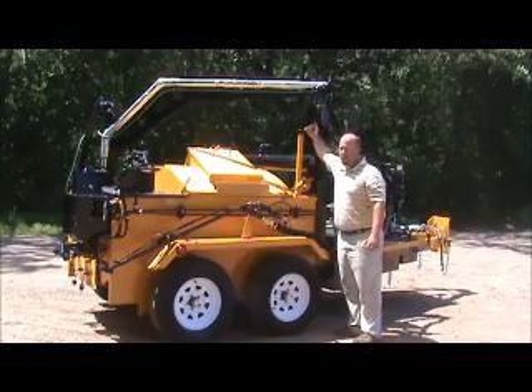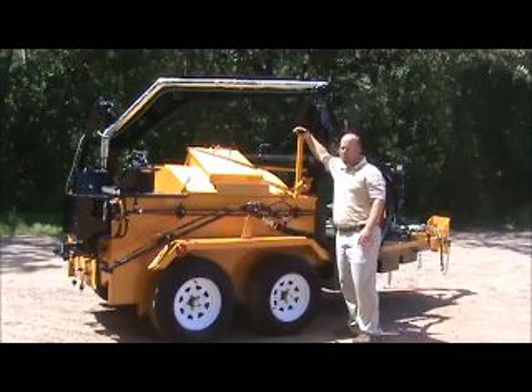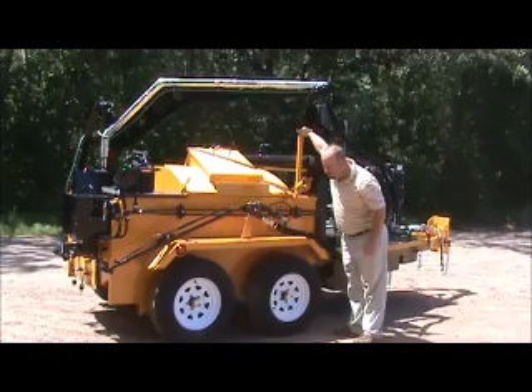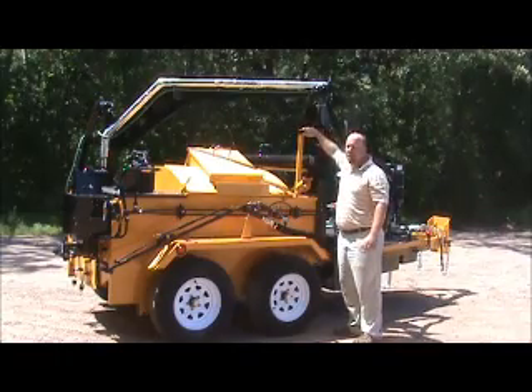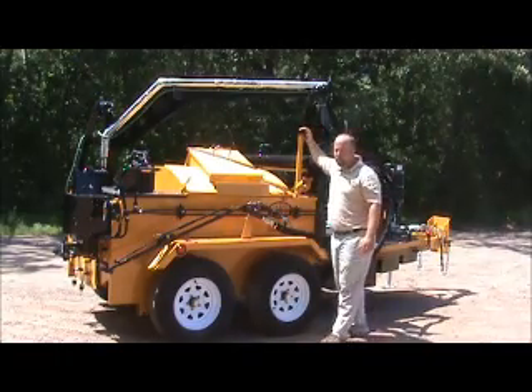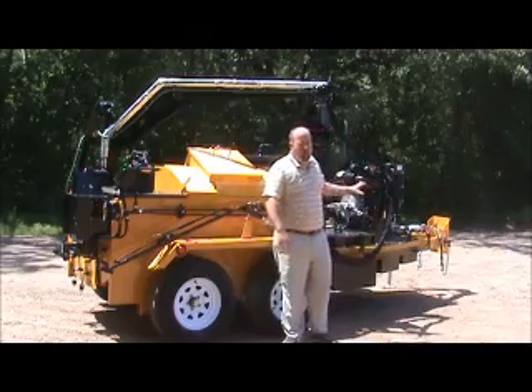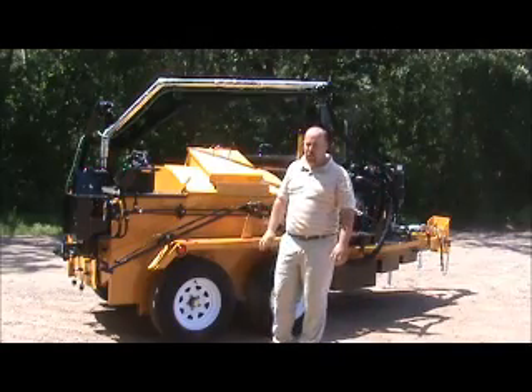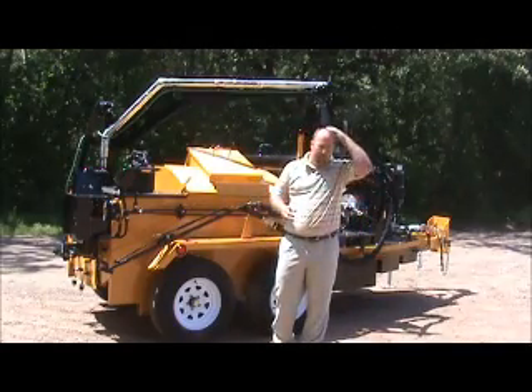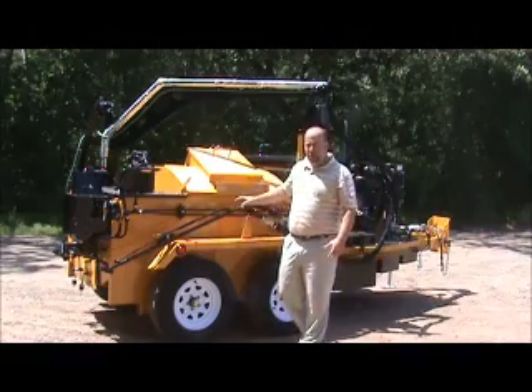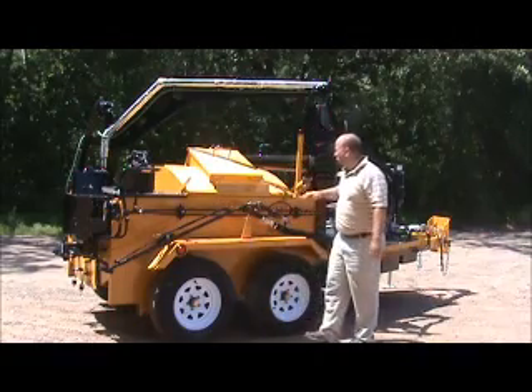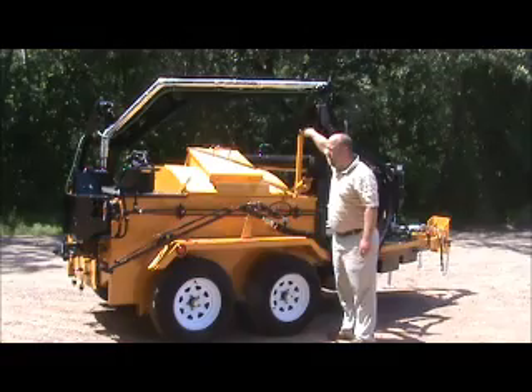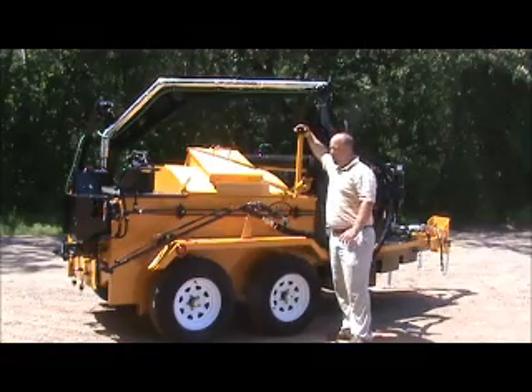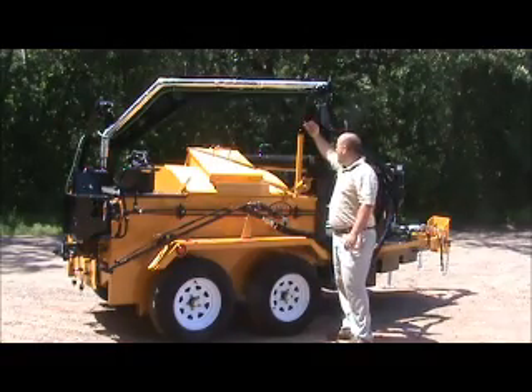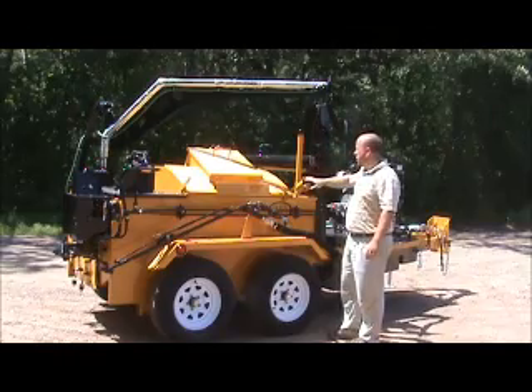We recommend that you change the oil, the heat transfer oil, every 1,000 hours or biannually. It's not as critical as engine oil. Engine oil, we recommend you change it at 100 hours, but as with any oil, it does start to break down, and it doesn't transfer the heat as well. So we do want you to change that. In this particular kettle, there's 85 gallons of oil. So I wanted to touch base with that.